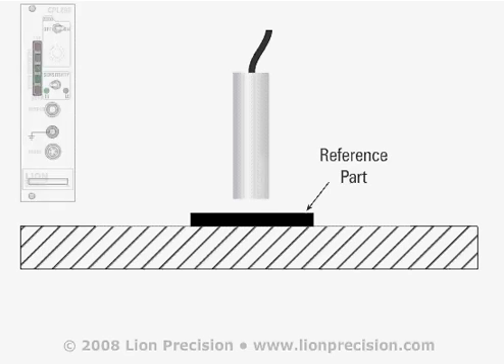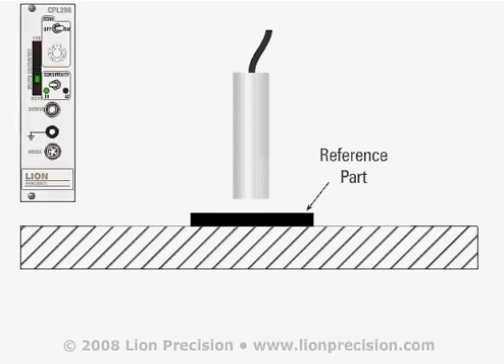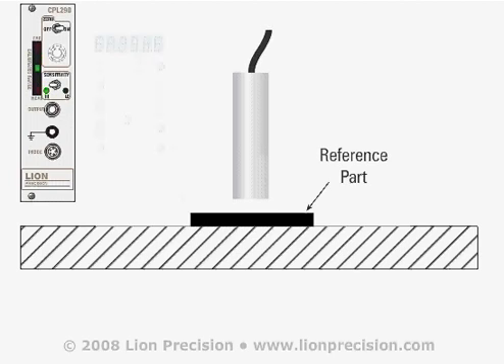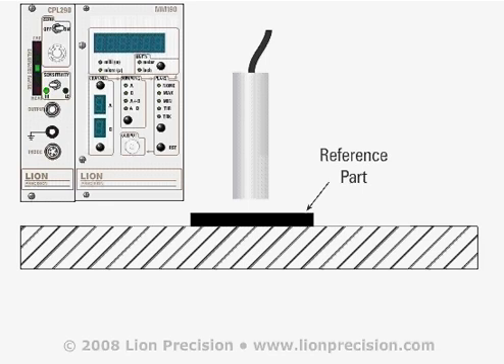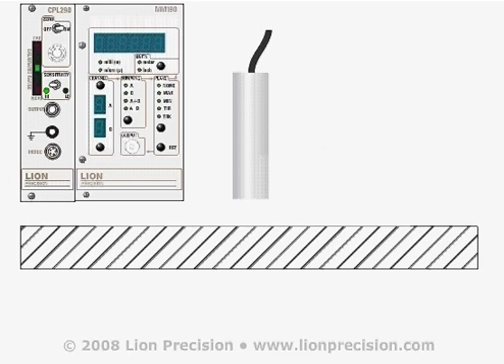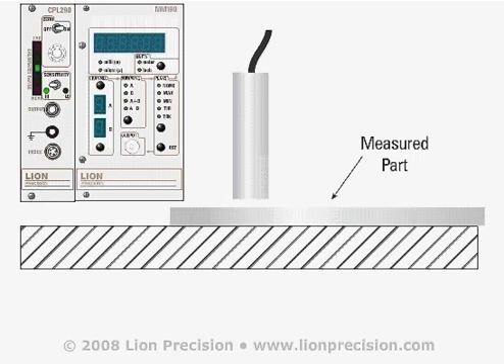To perform a single-channel thickness measurement, first place a conductive part of known thickness on the reference surface. Then adjust the sensor to measure the top surface of the part. The sensor should be positioned near the center of its measurement range to allow for positive and negative deviations from the reference measurement. Adjust the sensor output for zero volts, or a displayed reading of zero if a measurement display is being used. Then replace the reference part with a part to be measured and read the deviation in thickness from the display or calculate the deviation from the output voltage.